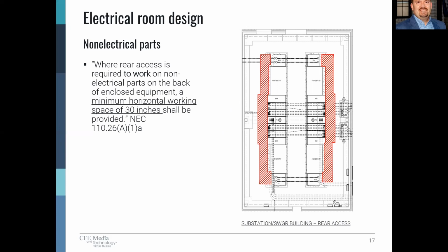You know, there are other examples like UPSs that often require rear access to get to filters for replacement and so on. There are a number of reasons why we need to provide rear access, and these can be to provide, you know, for the handling during removal and installation, but also to provide access for cable terminations and so on. And switchgear, as an example, there are physical barriers between the breakers and the bus, which provide a greater degree of safety and reliability. So we need to provide rear access to be able to get behind that barrier, that physical separation for cable terminations and such.